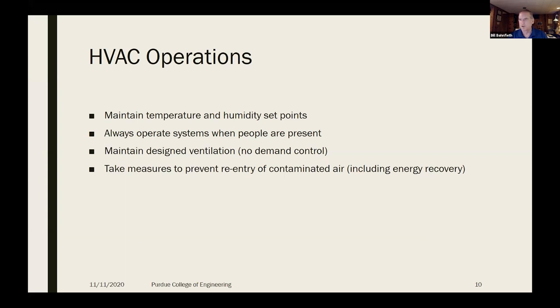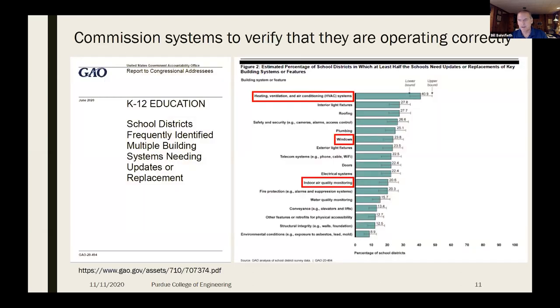And also, importantly, do things that will reduce the amount of recirculation. And this is an important point because initially we were saying, or some were saying, shut off energy recovery wheels. So you can operate them safely, but they have to be evaluated. And then a final point here, commissioning of systems is really important.